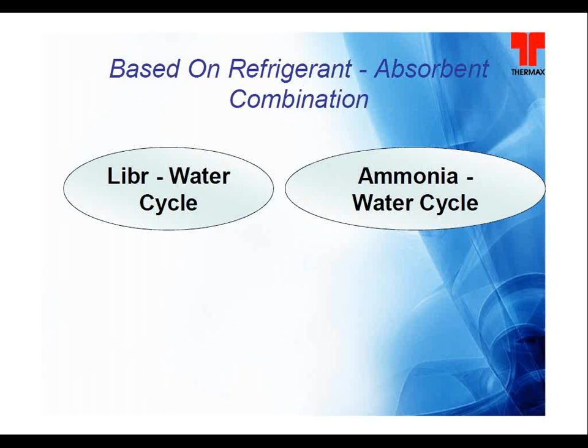I will be covering a couple of slides on how the vapor absorption machine works with lithium bromide and water as a refrigerant. So this is a slide which shows that this circle is nothing but the lower shell, and the left side is nothing but the evaporator and the right side is the absorber. In the evaporator, this blue color is shown by the chilled water. So the process water or the water which is coming from the air handling unit from your control room, VFD room areas where a certain temperature is supposed to be maintained throughout the year.